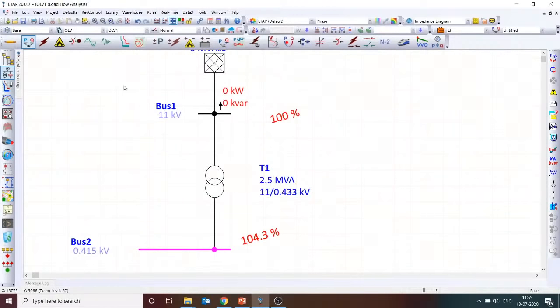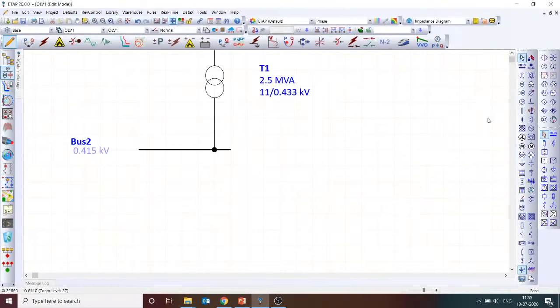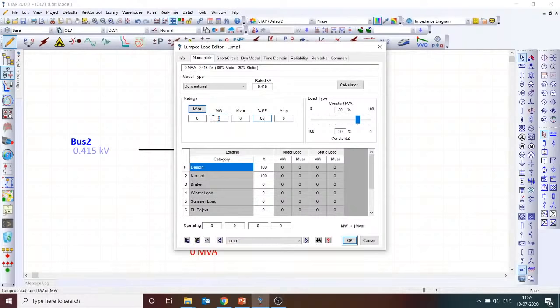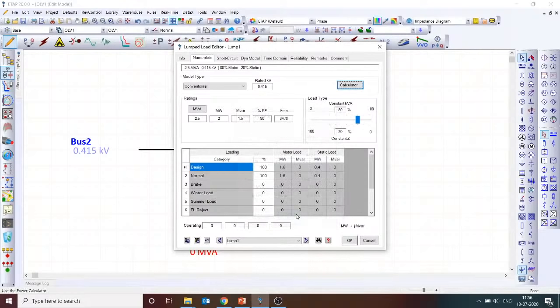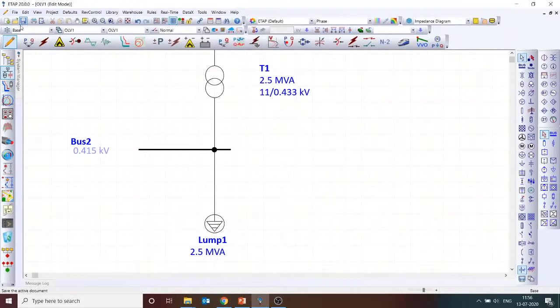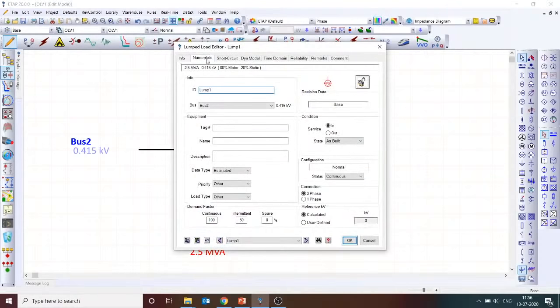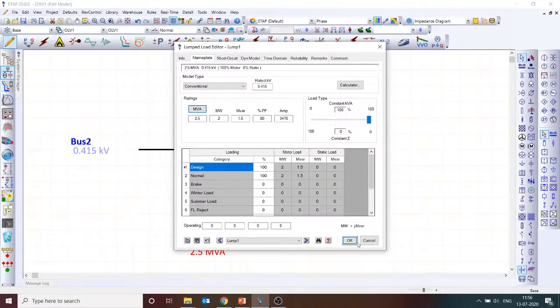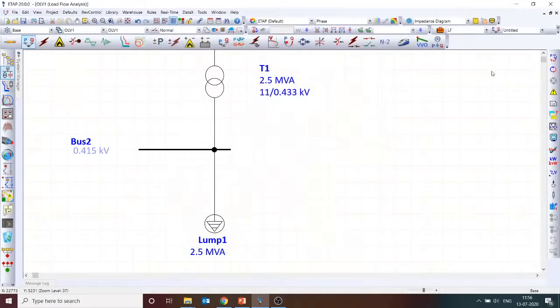So let me add a small load. For a 2.5 MVA transformer, I may connect, for example, a 2 MVA load at 0.8 power factor. Let me connect 2 megawatt at 0.8 power factor, so keep power constant and change the power factor to 0.8. That's exactly 2.5 MVA load. I'm trying to load this transformer to 100%. So let me go ahead with the load flow. I'm running a load flow analysis.